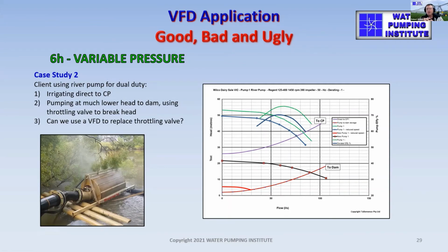Now, when that pump wasn't required to be pumping direct to the center pivot, water was diverted from that same rising main to a dam, from a river system which could only be pumped when the river was flowing. The water authorities say you can pump from this river system from November to end of February, and so during that period you pump like mad so that you can get as much water as you can within your allocation, of course. So what this farmer did, when not pumping to the center pivot, was throttle a valve, and this system curve here represents the same pipeline to the dam. So we've got a much lower lift. That's the only difference. The resistance is the same.